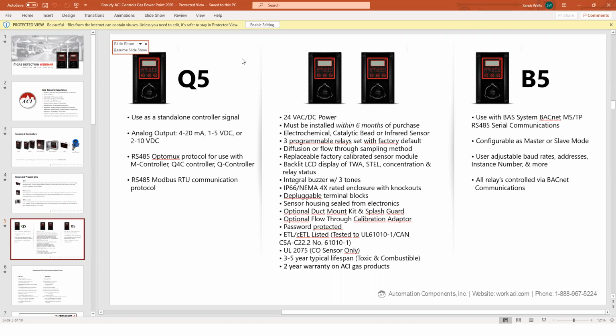It all depends on the concentration of gas. If it's real heavy concentration, it's going to degrade the sensors, no doubt about it. In a typical parking garage, it's going to last a lot longer than the typical specification, just because there's not going to be that high level of concentrated gas in that area. Now if you get methane or hydrogen or something like that, where it's always degrading the sensors, it's typically not going to last that long. But that's kind of the theory behind all the gas. 2-year warranty on all of our gas products too, as you guys well know.